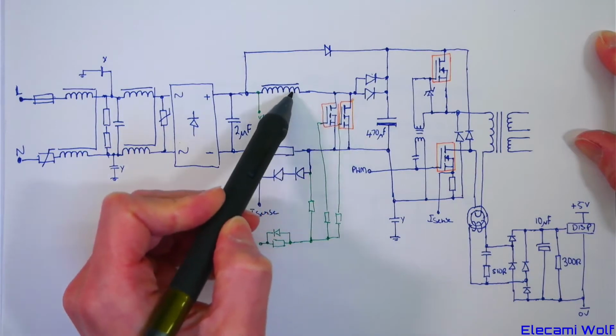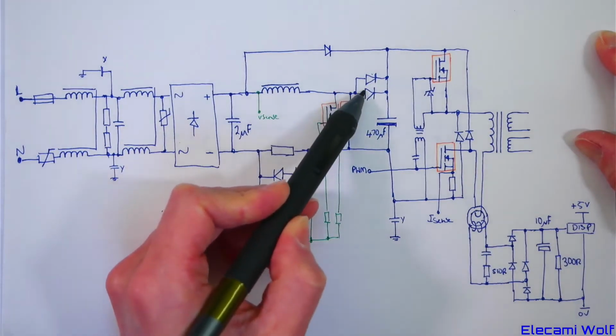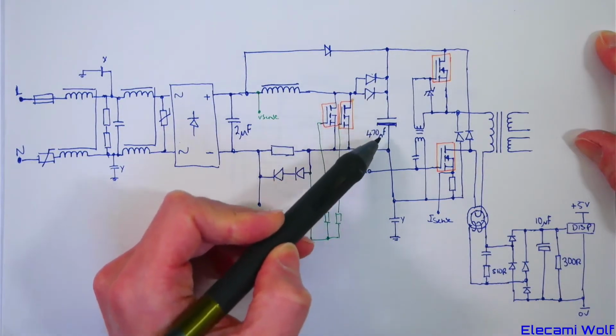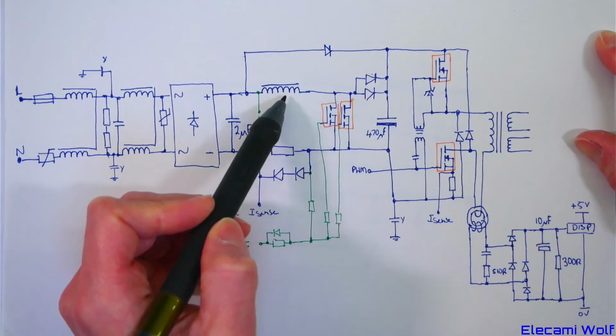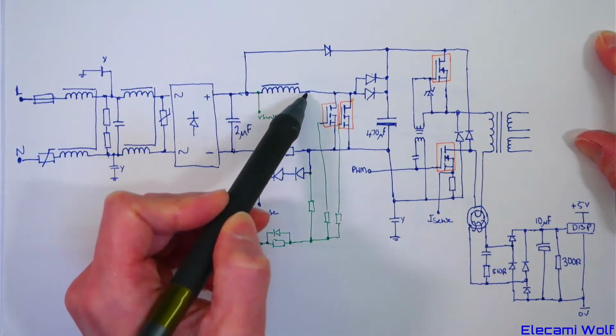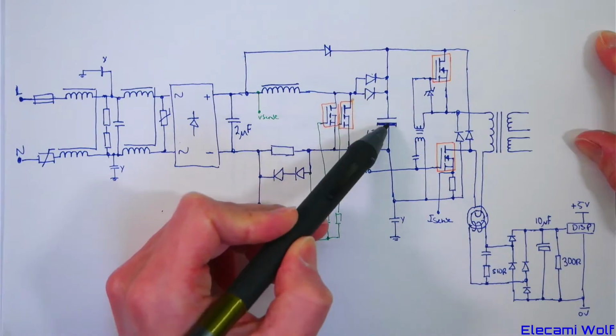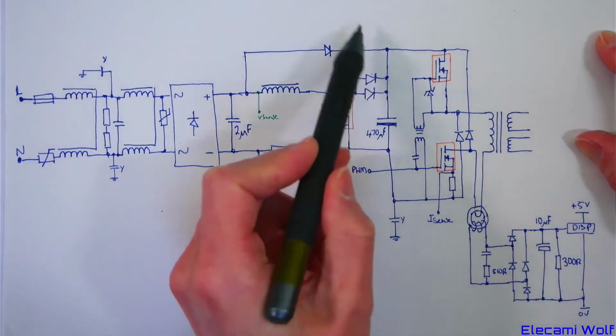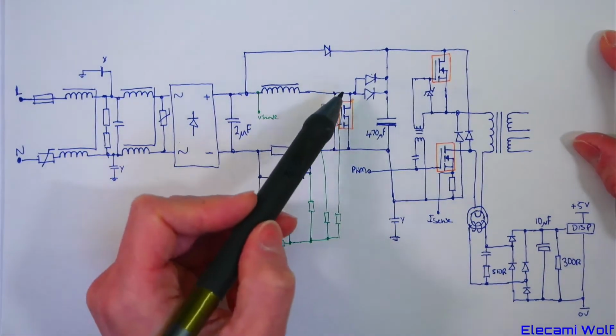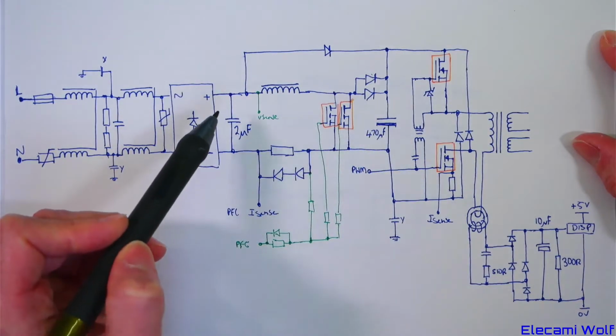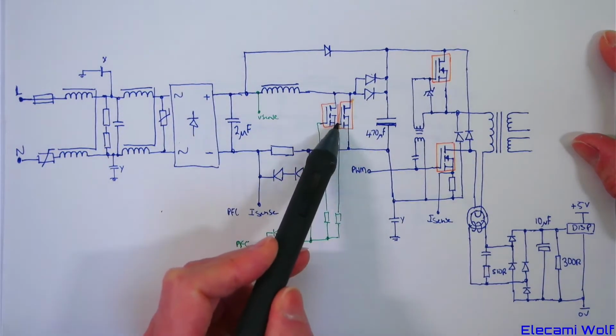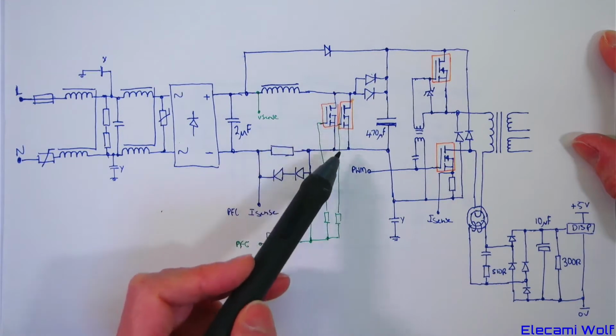The FETs are now off. The only way the current can flow is through these diodes and into the main DC bus capacitor, where the boost comes from, because the inductor will produce whatever voltage it needs to cause that current to flow. And there'll be voltage sensing off of that, so that it ends up regulating at a voltage that's higher than the peak mains input. There's two FETs in parallel to handle the peak currents required.